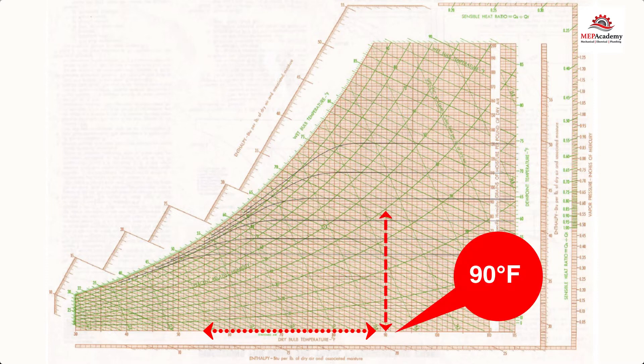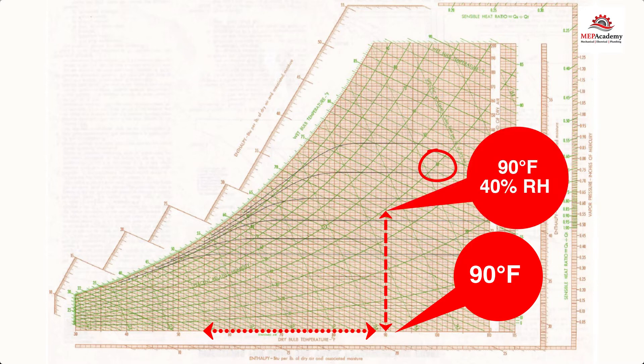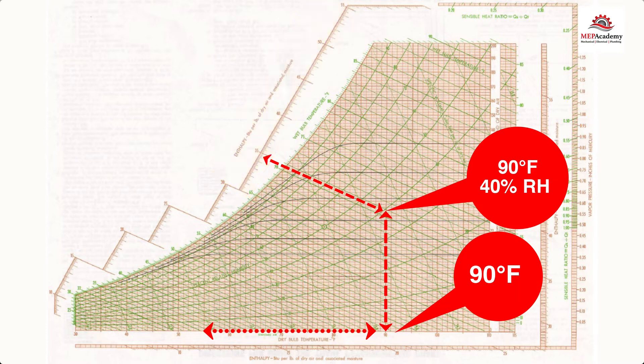From there until we hit our 40% relative humidity line, and then diagonally to the left until we intersect the enthalpy line. Here, we get an enthalpy of 34.9.